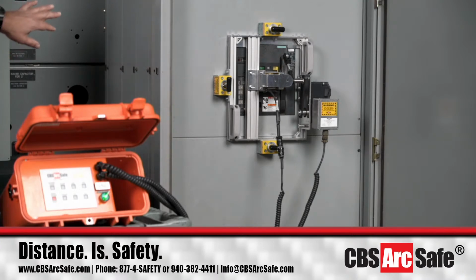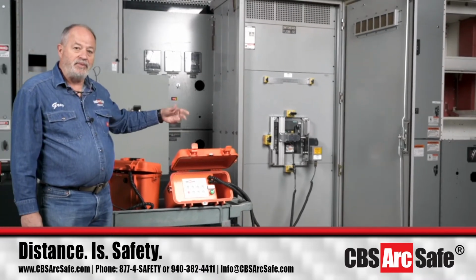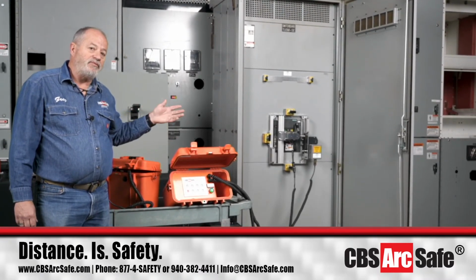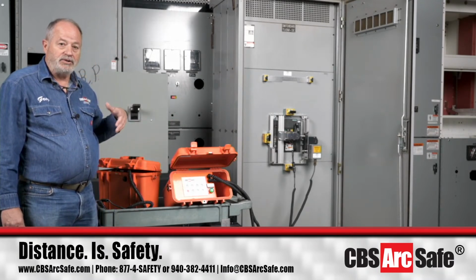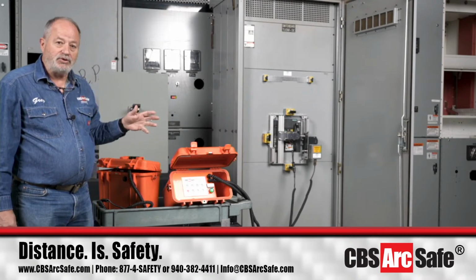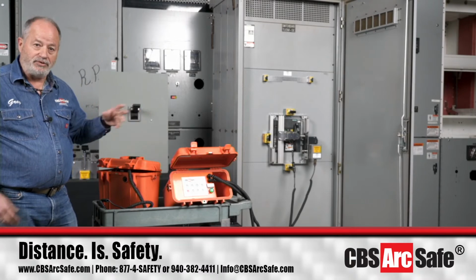And we can see that the breaker now has the spring charged because the flag is now yellow for the charged spring. Always remember when you're talking to us to also mention what your arc flash hazard boundary is. Because you could have a breaker like this in a room and potentially have the arc flash hazard boundary be the room. If you need one of our radio remote systems to be outside of the room while you do this operation, we have that capability, and that would get you out to 100 meters away from the piece of switchgear, as long as you've got a good radio path to the switchgear.